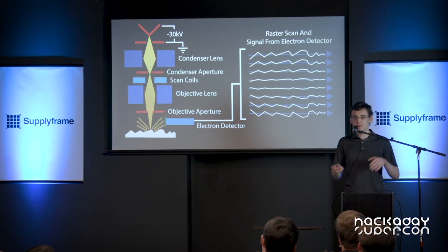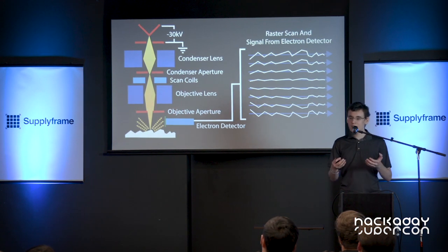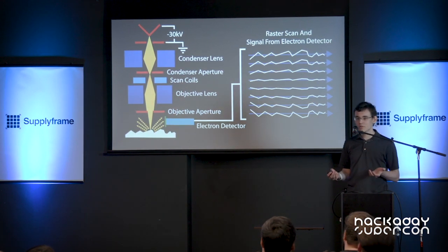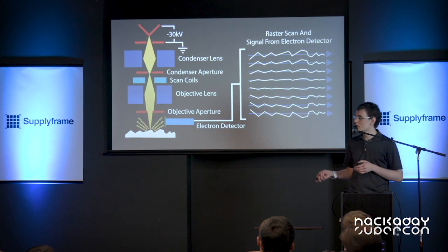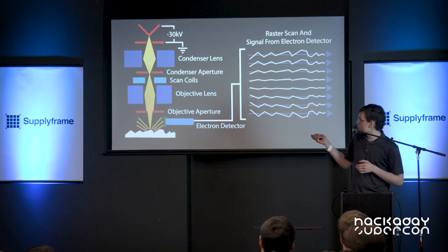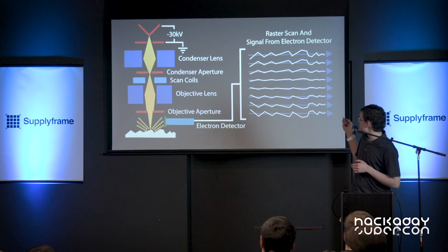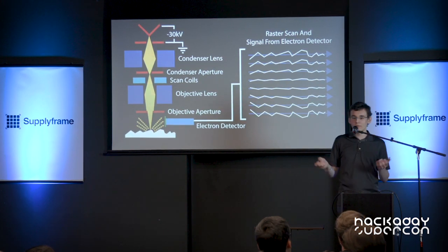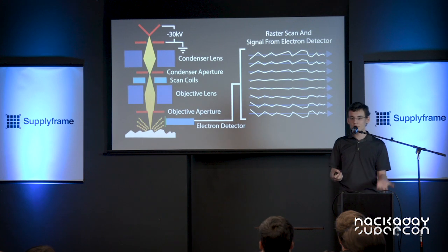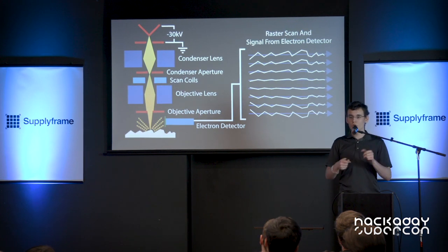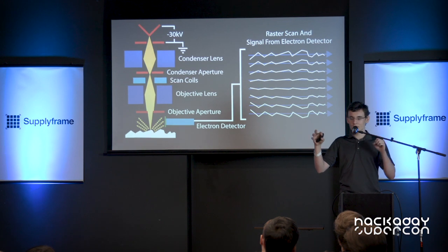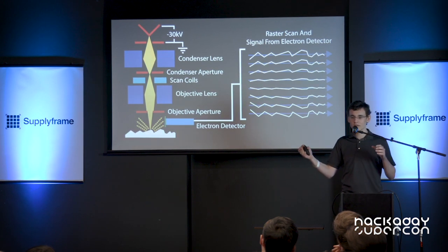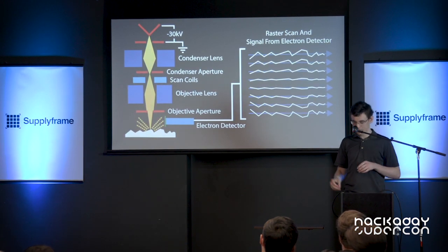Once the beam strikes the sample, some electrons are given off by the sample. An electron detector picks up those electrons and transmits them to the screen. Using the scan coils, we scan the beam in a raster pattern across the surface of the sample. At every point, we record how many electrons come back off the surface, correlate that to brightness, and make the beam brighter or less bright on the CRT — and we're left with an image.